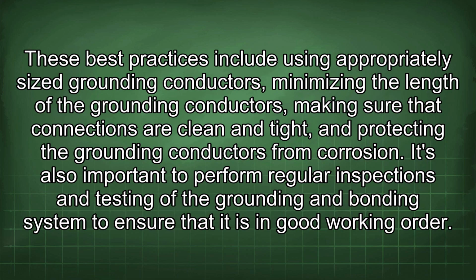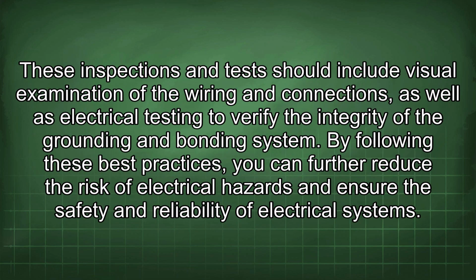In addition to the NEC requirements, there are also industry best practices for grounding and bonding. These best practices include using appropriately sized grounding conductors, minimizing the length of the grounding conductors, making sure that connections are clean and tight, and protecting the grounding conductors from corrosion. It's also important to perform regular inspections and testing of the grounding and bonding system to ensure that it is in good working order. These inspections and tests should include visual examination of the wiring and connections, as well as electrical testing to verify the integrity of the grounding and bonding system.